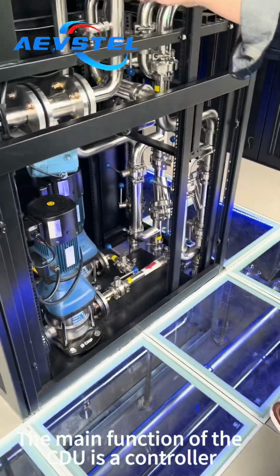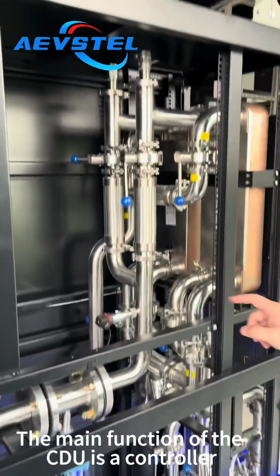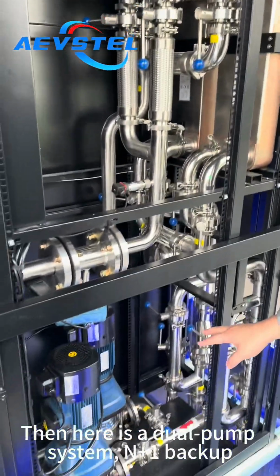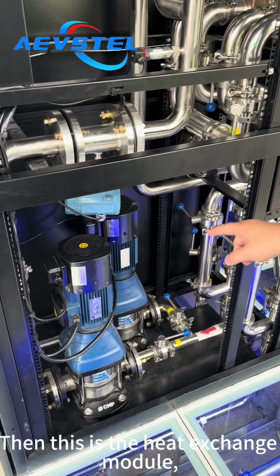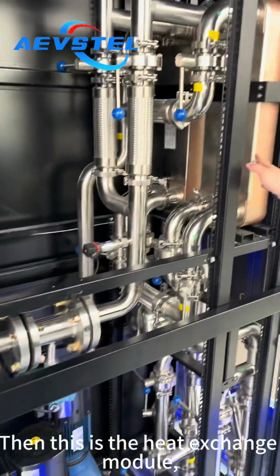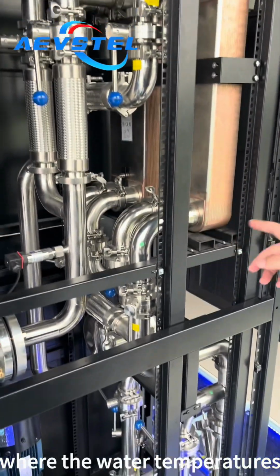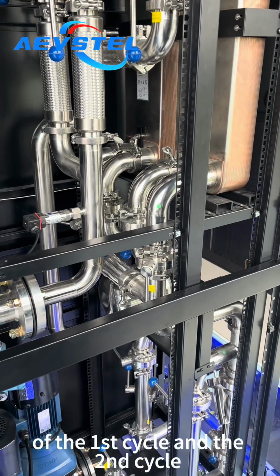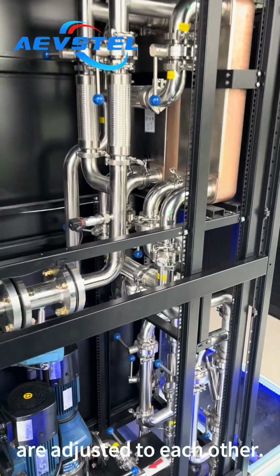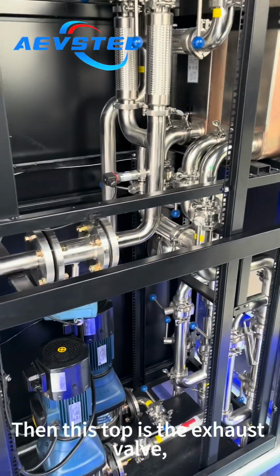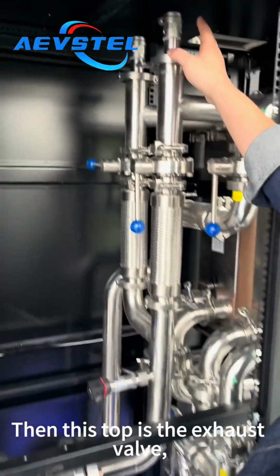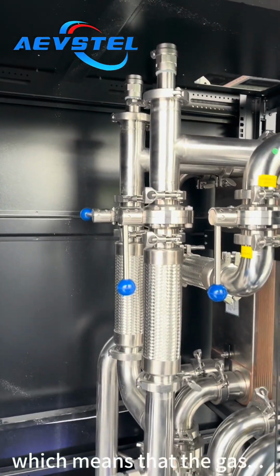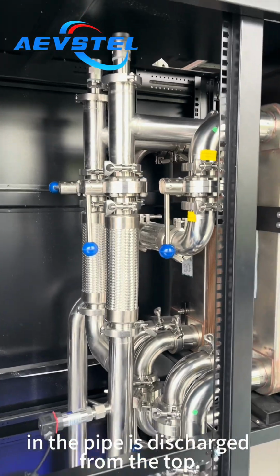The main function of the CDU is a controller. Then here's a dual pump system, N+1 pump. This is a heat exchange mode where the water temperatures of the first cycle and the second cycle are adjusted to each other here. Then at the top is the exhaust valve, which means the gas in the pipe is discharged from the top.